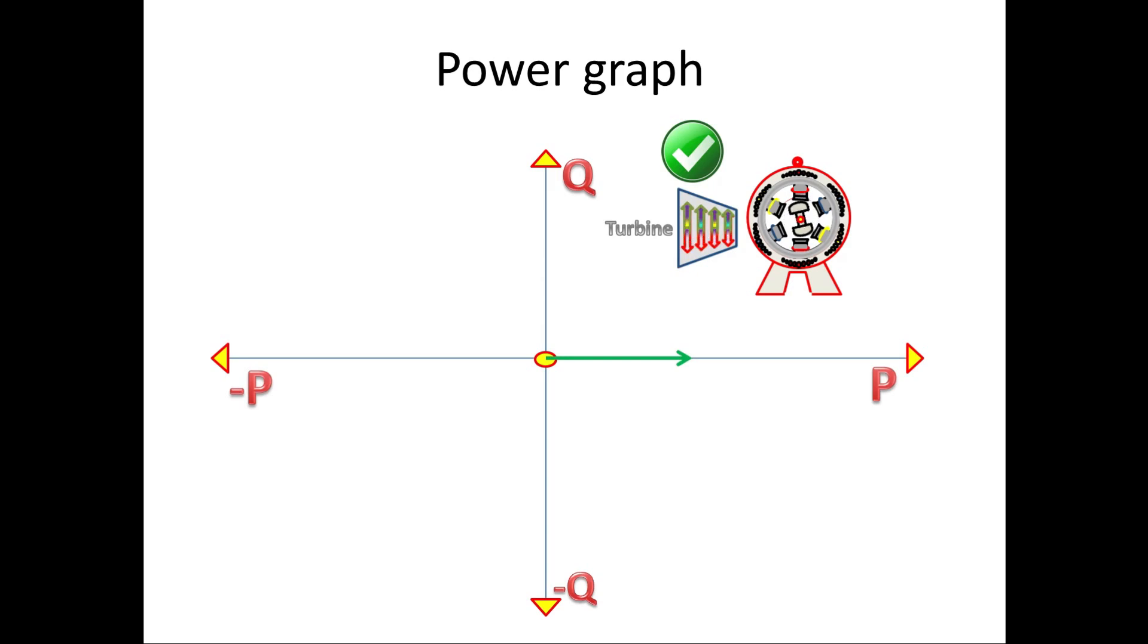Due to this, the power will be positive, that is P is positive. And if exciter is also in good working condition, then the rotor produces high magnetic field. Due to this effect, it will deliver VAR to grid. So Q is also positive. Since P and Q are positive, the operation comes under first quadrant.